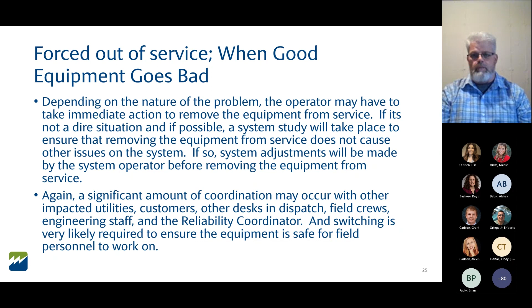And so here's a situation where we found some equipment. It was good equipment, but it's having a problem. Rather than waiting for it to fail, we're going to take some proactive action, take a look at the equipment, take a snapshot of the system, and see how it looks. Again, with any type of problem, there's going to be a tremendous amount of coordination that has to happen with utilities, customers. Is it going to impact load when we take this equipment out of service? Do we have to drop load? Is it impacting maybe station service at one of our substations or a power plant? Those type of things. And if switching is required, we're going to have to make sure that the equipment is safe enough to operate, especially if we're getting into pressures on circuit breakers and those type of things.